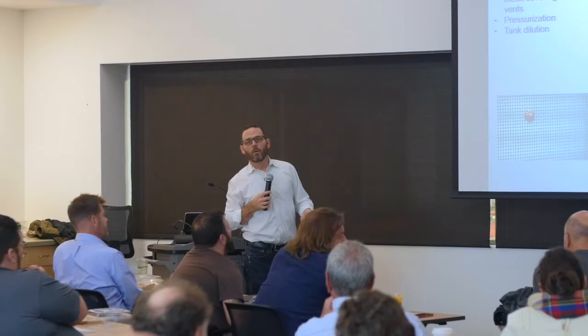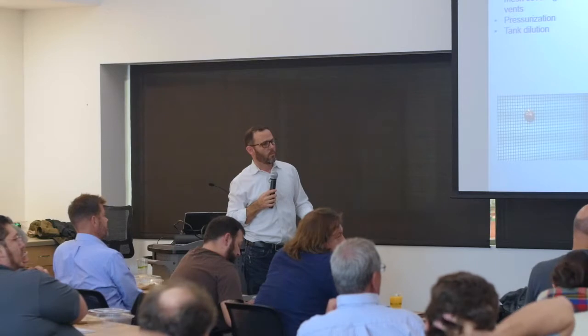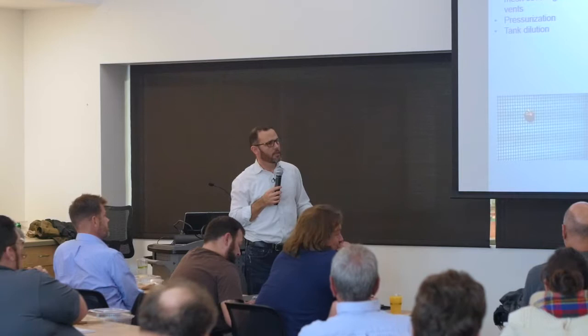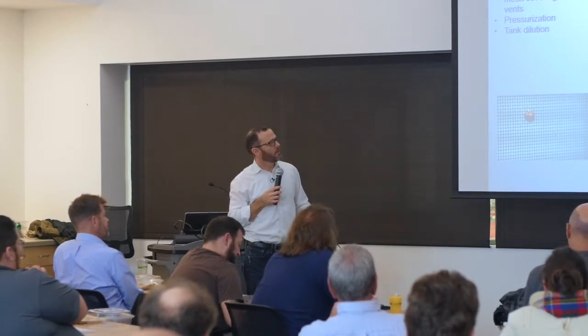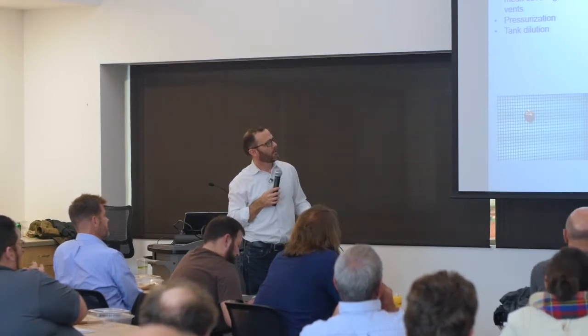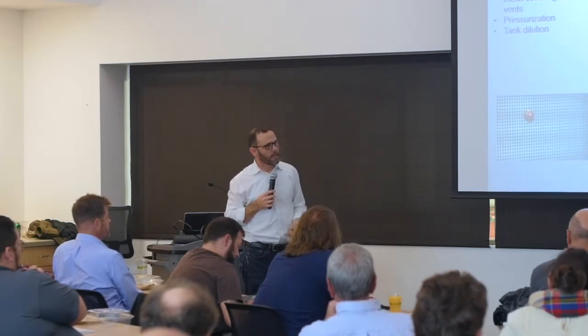Do you have a lot of saturation points? Not too bad. This is in the building, right? Yes, it's in the building. No condensation problems on the glass. In the morning, it would get some condensation once it got up, but it's pretty well controlled. And remember, early on, all we had was this waterfall system. Later on, we did another project where we introduced the dry steam humidifier into the air handling system. And so we humidify the air directly.